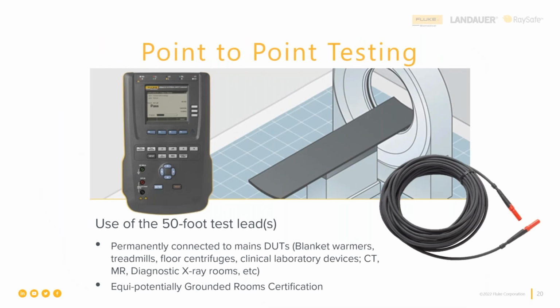All right, how about things that are permanently connected to mains power, or equipotentially grounded rooms where we, at least before we start using that room, have to show that there are no ground loops, and that the equipotential grounding actually causes all current flow to move to a dedicated ground that comes only into that room and nowhere else. So to do those kinds of tests, we need to use a mode of testing on our safety analyzers called point-to-point testing.